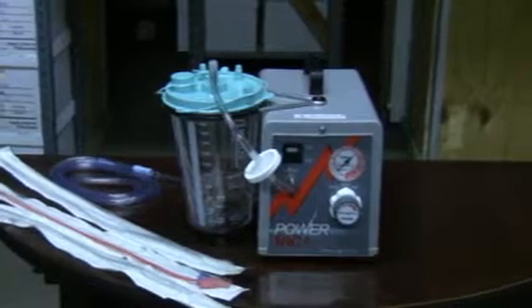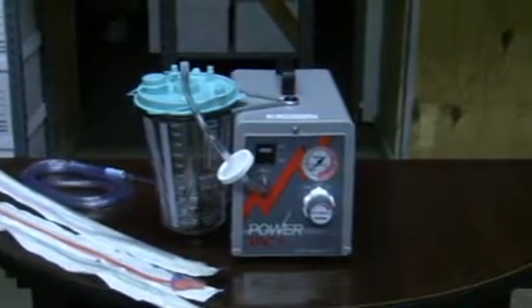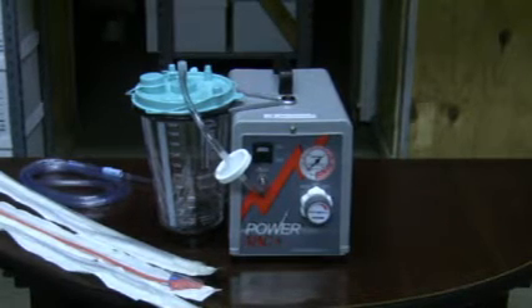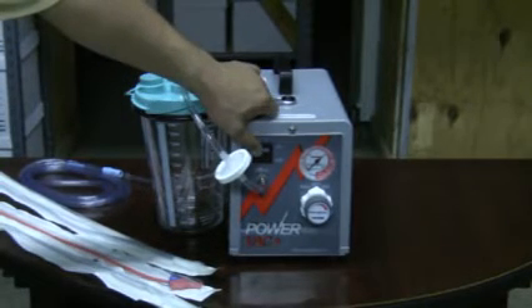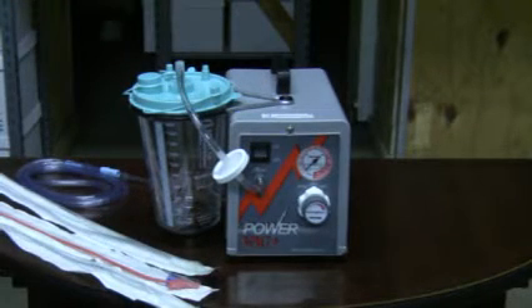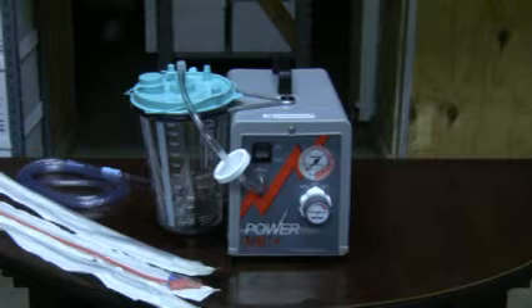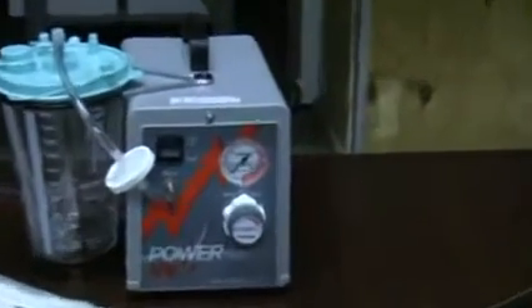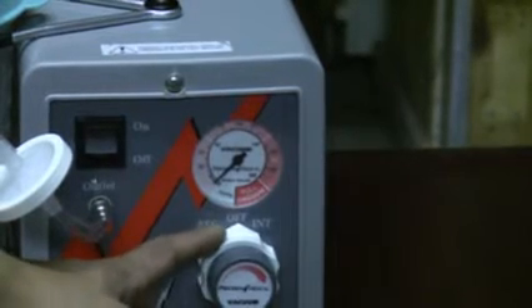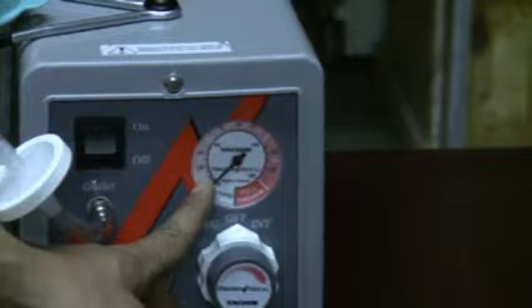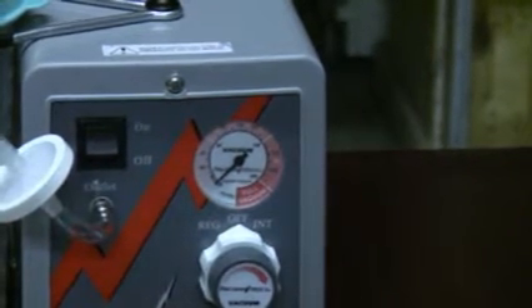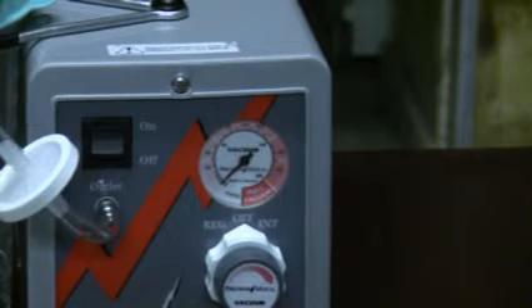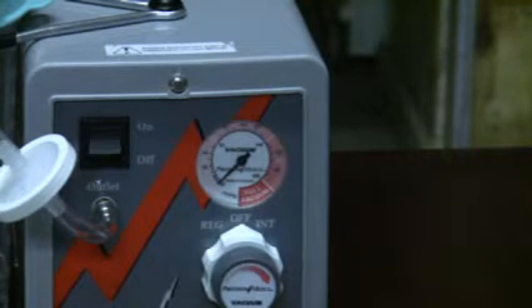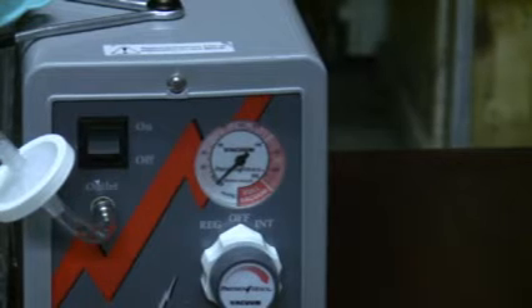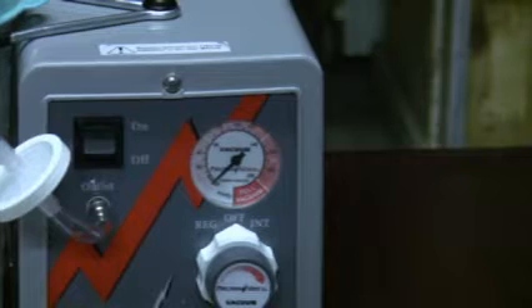There should always be at least 4 inches of space around the intermittent suction machine at all times while in use to help with cooling of the actual intermittent suction machine. When powering on your intermittent suction machine, you can power on and actually hear the motor running. However, if your vacuum mode selector is selected in the off position, there will be no vacuum pressure present on your vacuum gauge. For any continuous suction procedure, you would need to use your white vacuum mode selector and select regular for continuous suction.